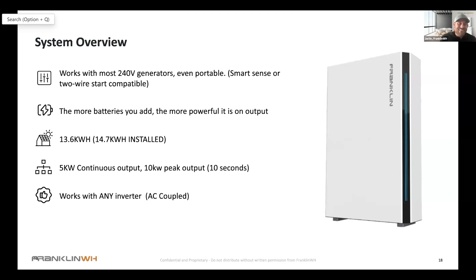We did what we could to prepare you for this. We tested out the system, lit it on gasoline, dropped them off of cranes, submerged them in seawater. You've got your UL 9540A, and the new A-gate will actually have, for those wondering, the 1741 protection pass-through on the label of the A-gate. You will not have those delays anymore with the AHJs that give you a hard time.